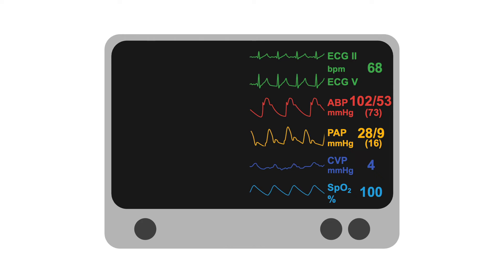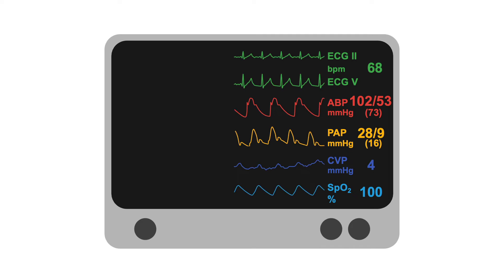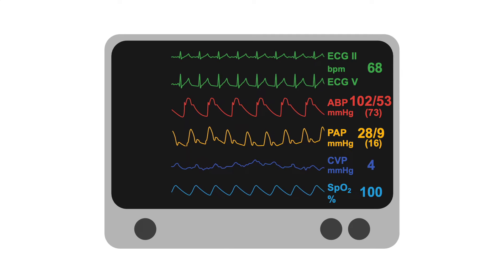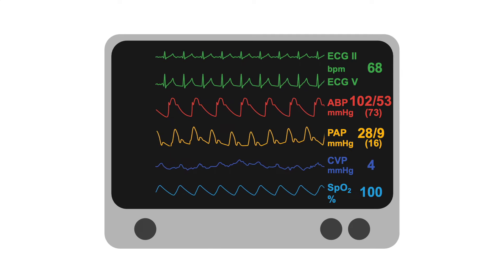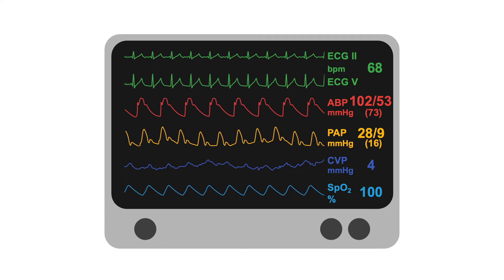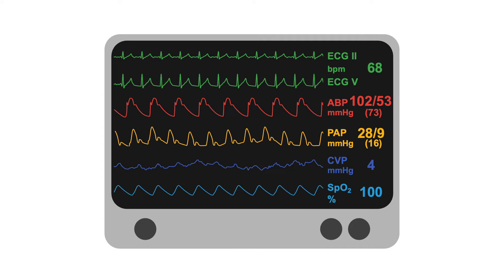Let's see what this actually looks like on a patient monitor. Each channel is labeled for easy reference. You will also notice automated computer measurements of arterial and venous pressures. These measurements are useful at a glance, but remember, all pressure measurements are sensitive to gravity and positional changes, so it is crucial to level and zero the system each time measurements are obtained in order to be accurate.